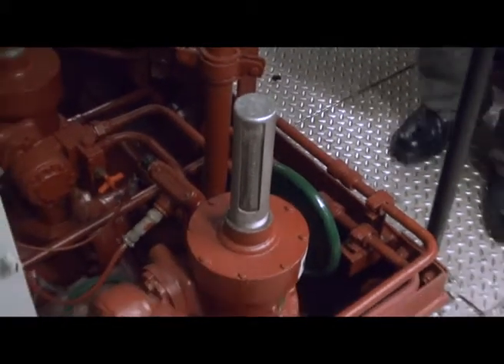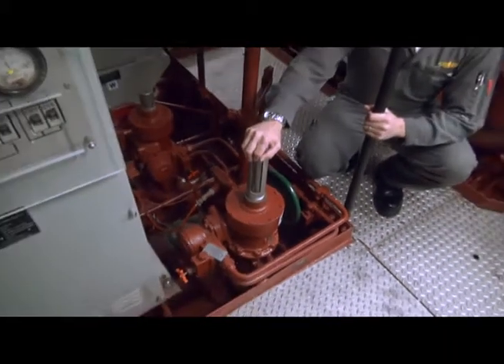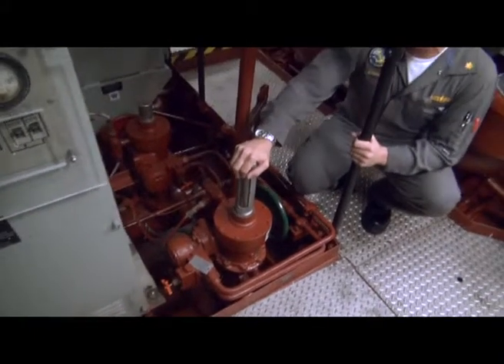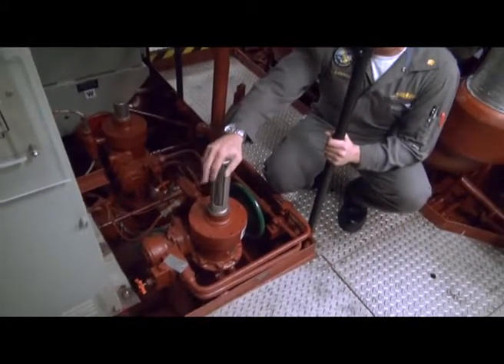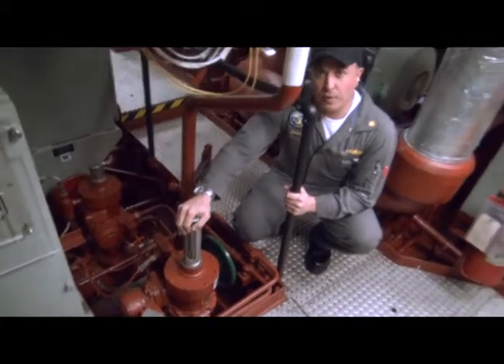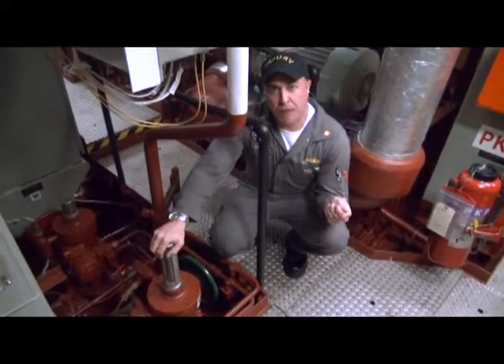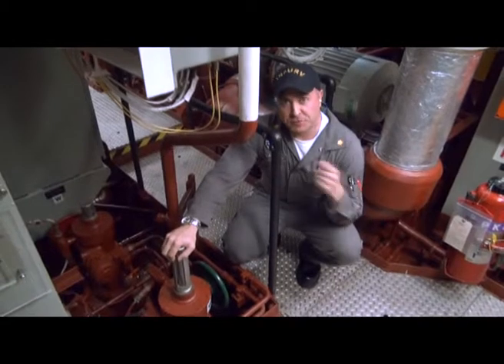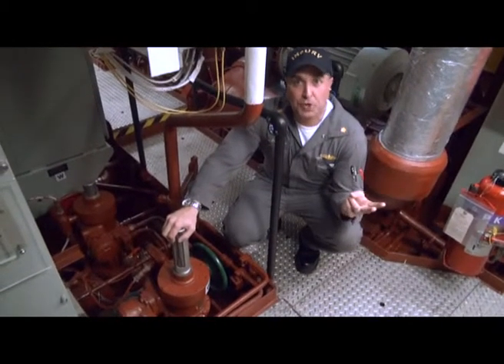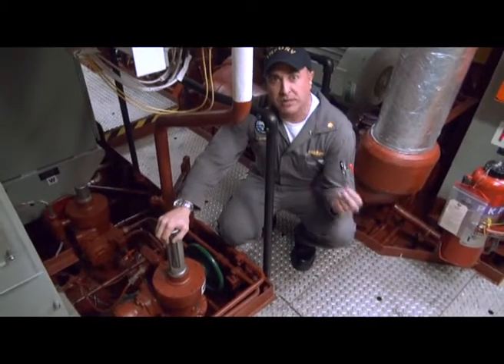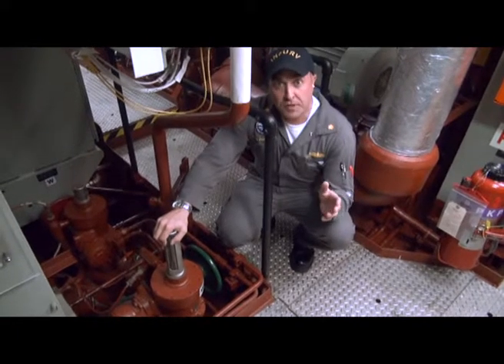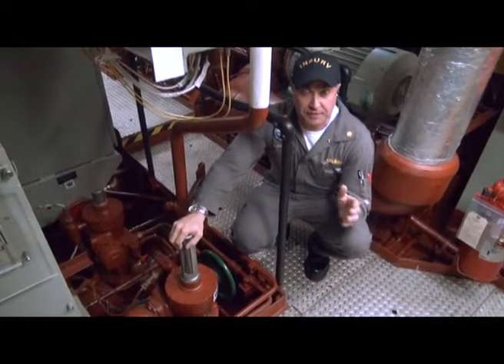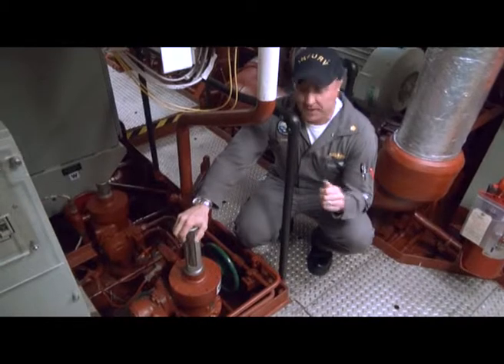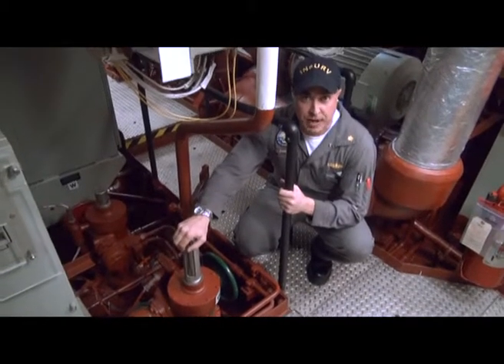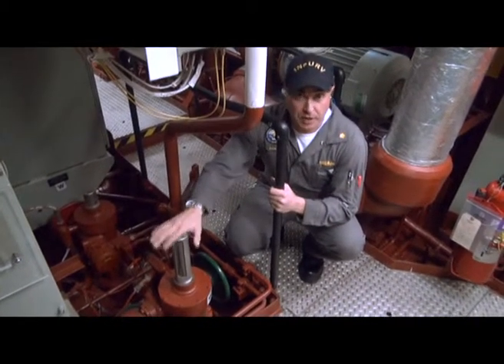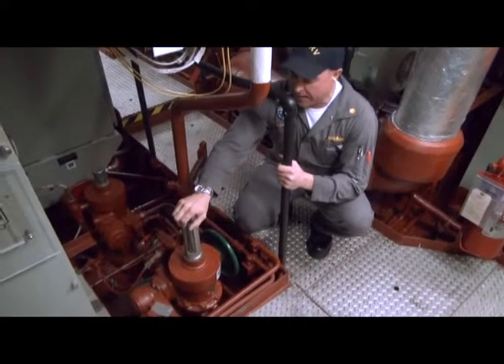In this case, we'll shut this valve, and the best way to check the suction interlock is to actually shut the valve remotely, and then try to start the pump locally and from CCS. On a DDG there are two places to start this pump, local and CCS. We'll try them both. The pump shouldn't start, obviously. If the pump does start, we'll secure it right away. That means we have a problem with this interlock, and that's an RBO. So we make sure we check those before we come out.